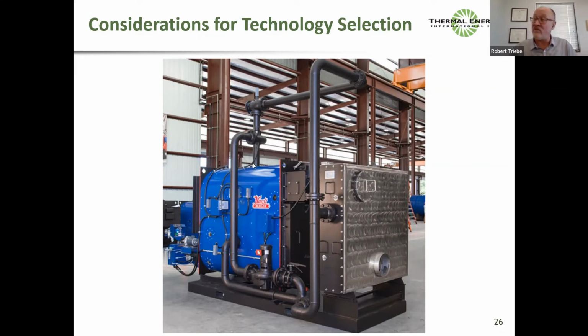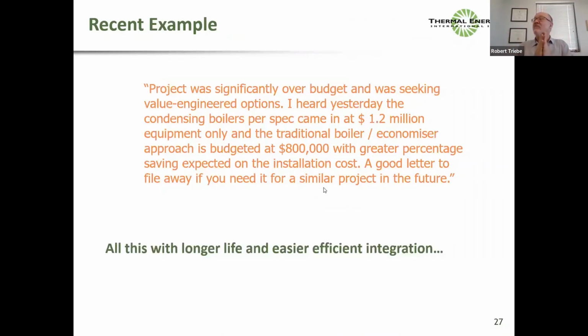And so this boiler will last 30 years, and this economizer will need some tube replacement, which is quite simple and can be done external to the boiler, and of course much lower cost. And it ends up being a similar size. And the reason for the performance difference is if you hook this up to a hospital, for example. Actually, I think the graphs coming up display that better. But here's a recent example. This is an example where I'll just read it.